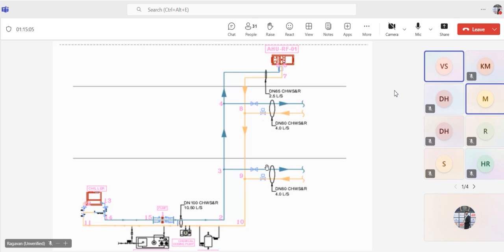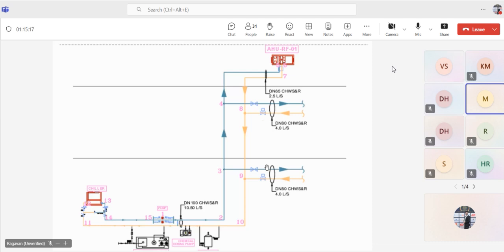Sir, how can we calculate the pipe size as per the flow? In the chilled water system, for pipe size, you know the velocity. Usually we go for 1.5 meter per second velocity, and based on that you can calculate the flow rate. Maximum you have to consider 1.5 meter per second velocity.